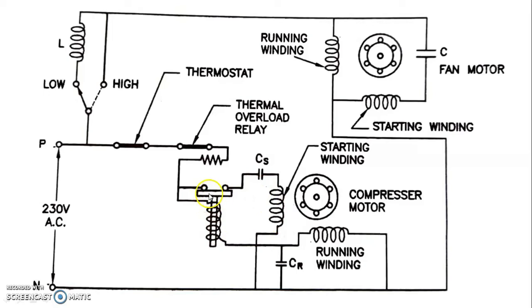For this we use one relay, which normally remains in the de-energized form. In due course of time it energizes and the contacts open, and the starting winding and starting capacitor are both disconnected from the circuit. We also have a thermal overload relay to protect the compressor motor. In case of overload current or short circuit, the thermal overload relay trips and it protects the motor.